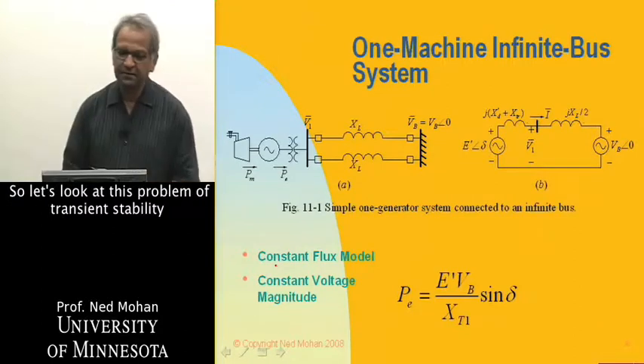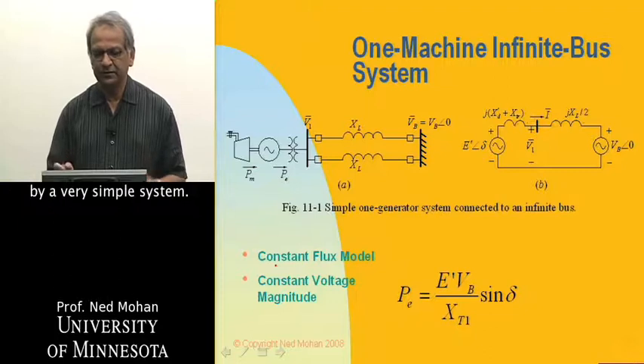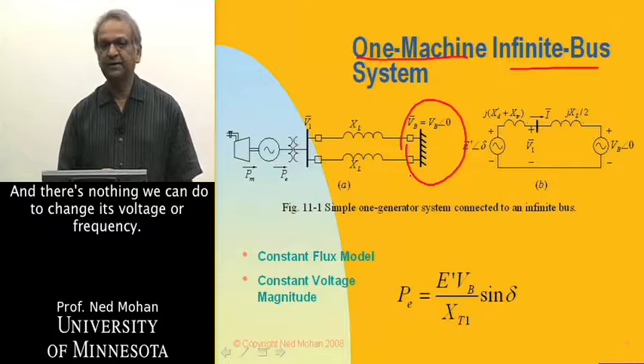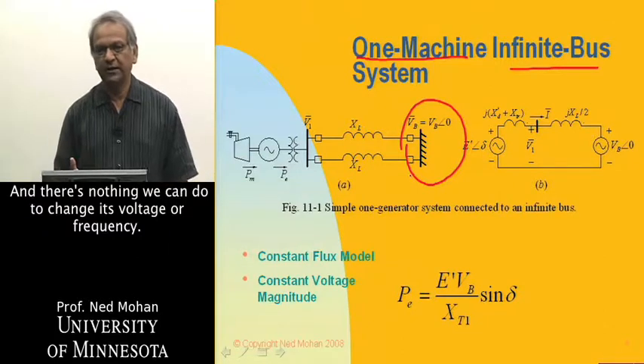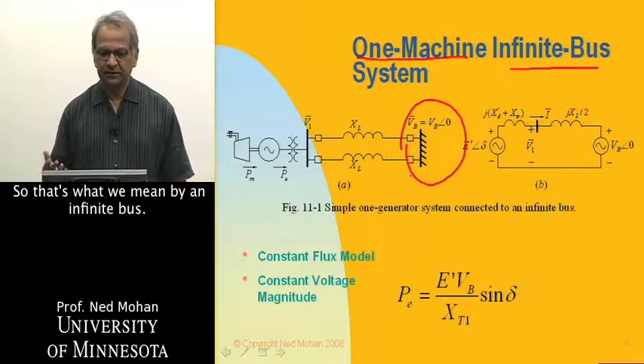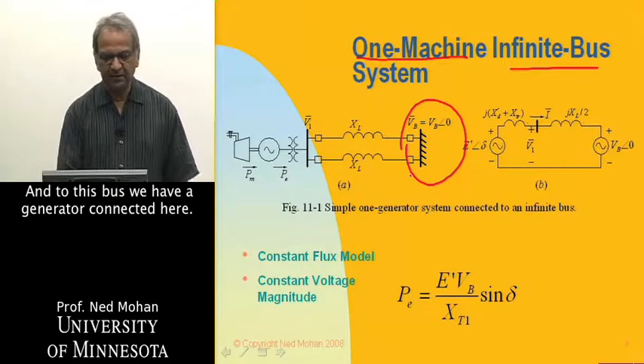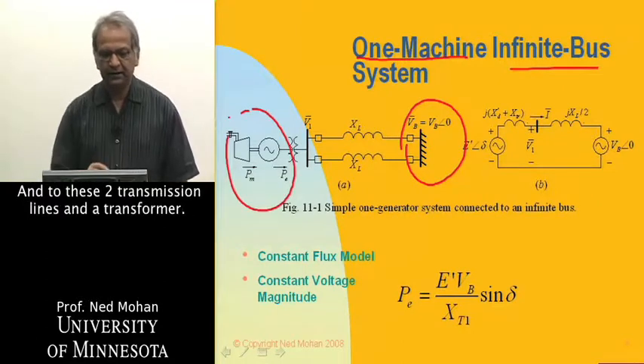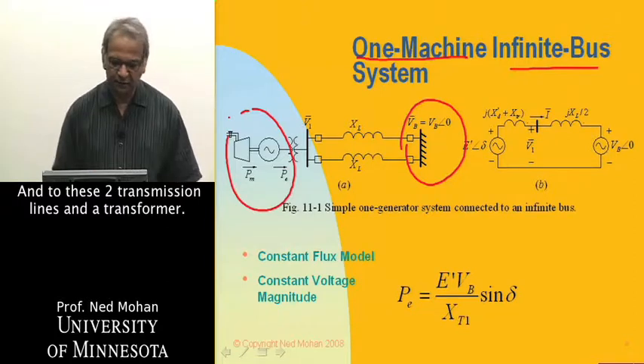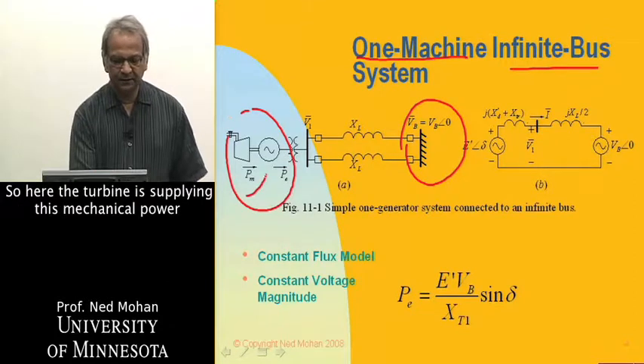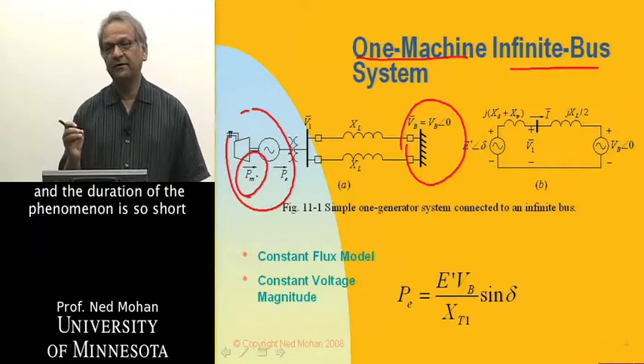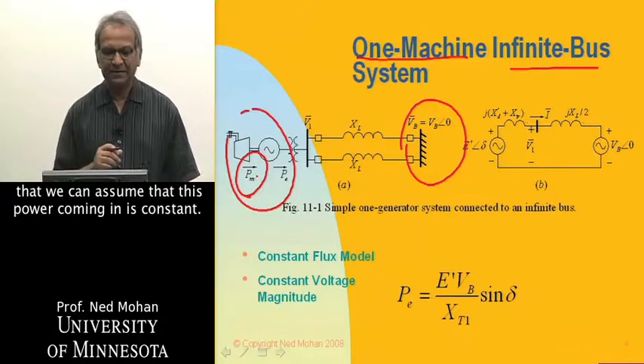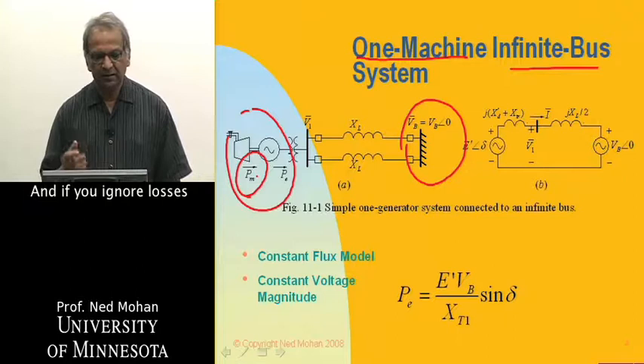Let's look at the transient stability problem using a very simple one-machine infinite bus system. The infinite bus has fixed voltage and frequency, with zero internal impedance. A generator is connected to this bus through two transmission lines and a transformer. The turbine supplies mechanical power, and the duration of the phenomenon is so short that we can assume this incoming power is constant. If we ignore losses, the electrical power given out equals the mechanical power coming in in steady state.